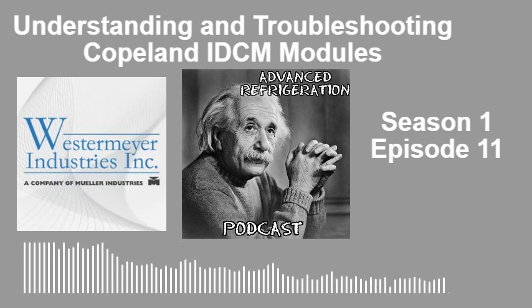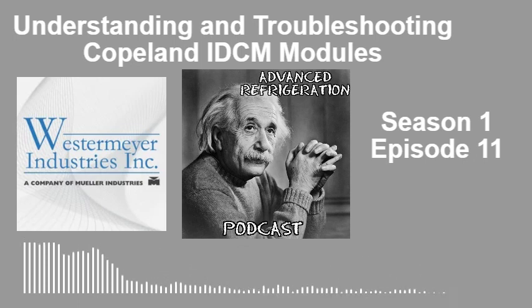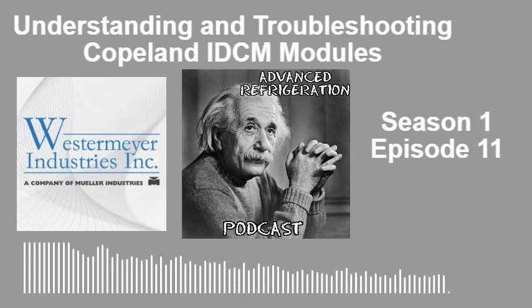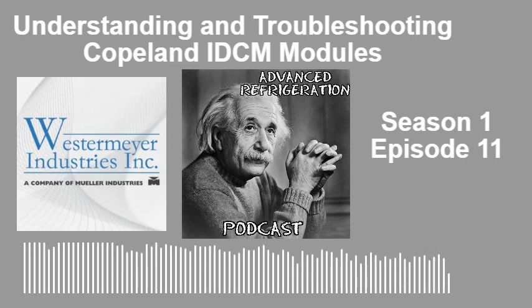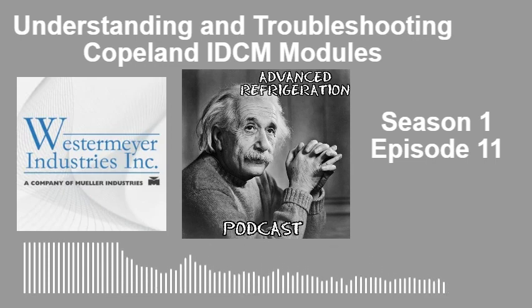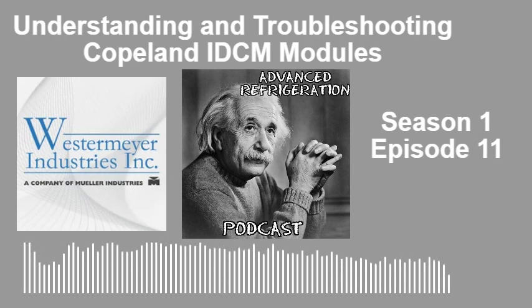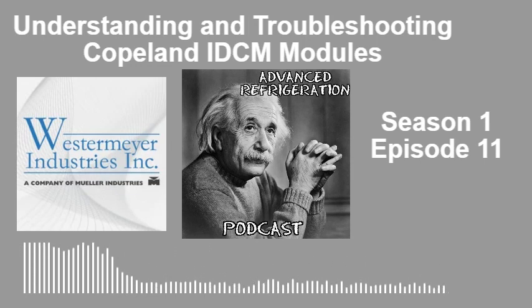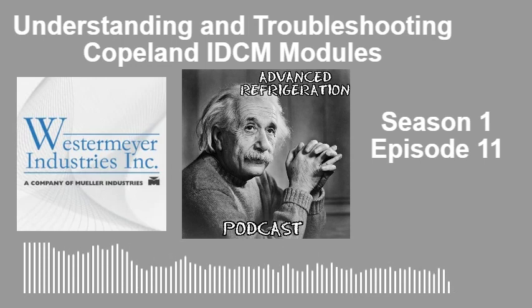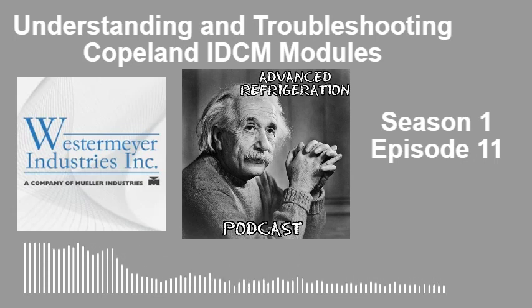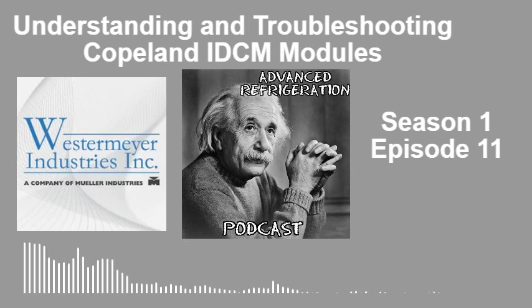Well, these guys, nobody could figure it out. They replaced a bunch of boards and they kept failing. And basically what happened was they were blowing up the analog output cards in the CPC controllers. So some of them would blow up right away. Some of them would last a week. Some of them would last a month, and they would blow up. They would blow up the output. So the first one I went to, I would get no DC voltage out of the analog output. So I swap out the board, turn it on, boom. Board blows up.